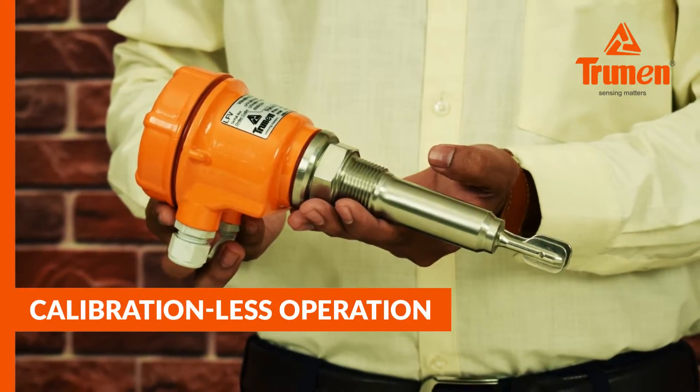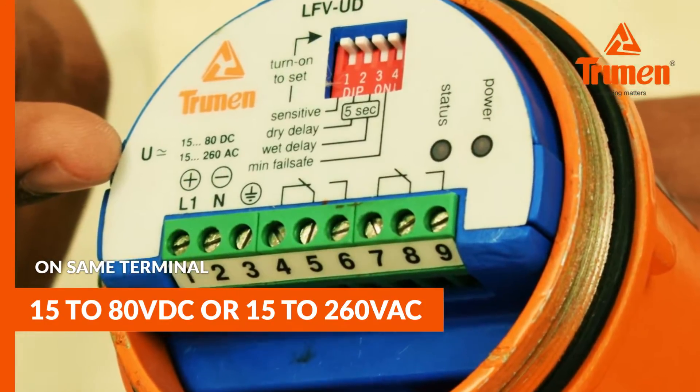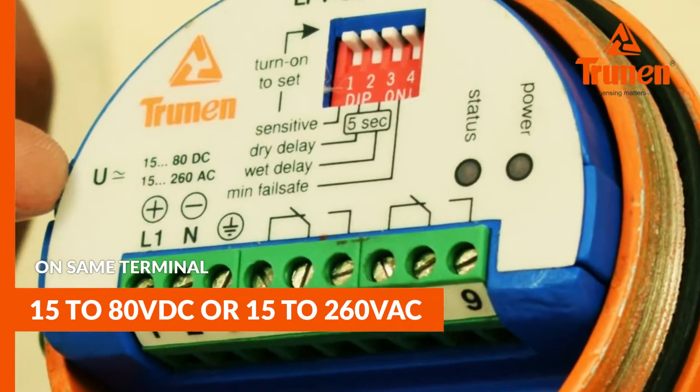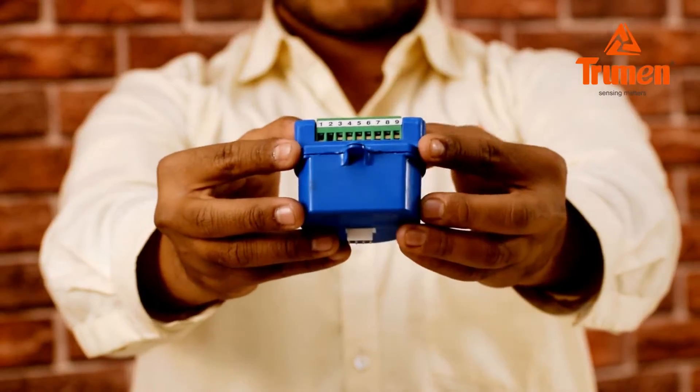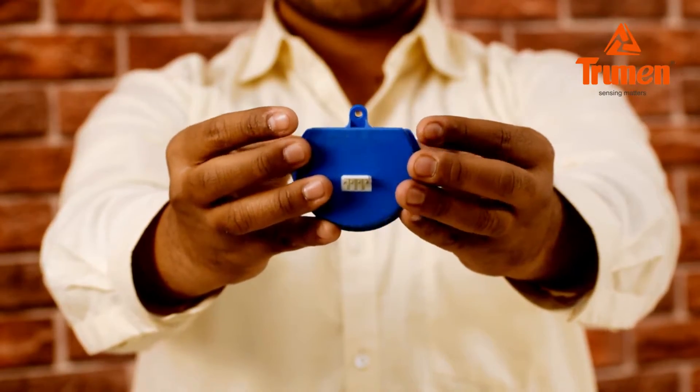The Trumen vibrating fork is compact in size with calibration-free operation. It features a universal power supply on the same terminal — 15 to 80 volt DC or 15 to 260 volt AC — an inbuilt settable switching delay of 5 seconds, a tropicalized sealed electronic module, and easy maintenance.